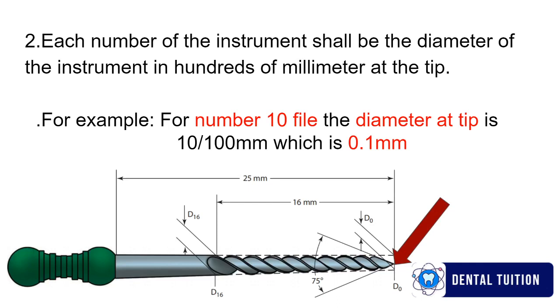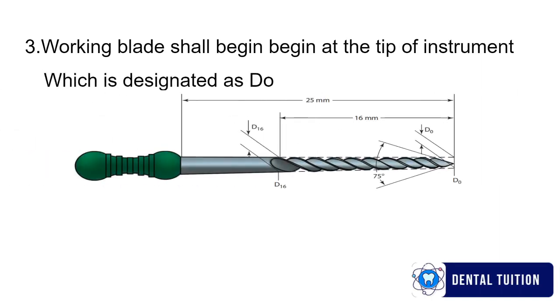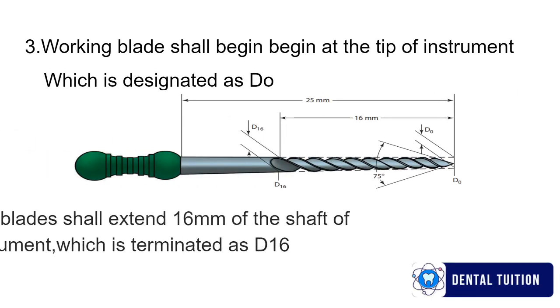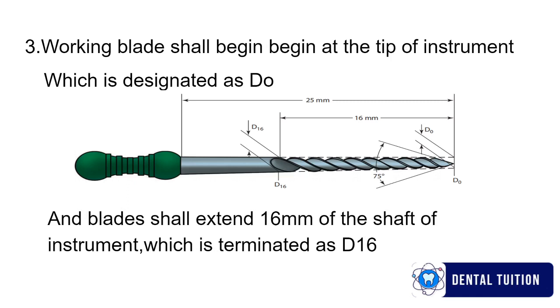Now next recommendation we are going to discuss is that the working blade shall begin at the tip of the instrument, which is designated as D0, and the blades shall extend 16 millimeters from the tip of the instrument, which is terminated as D16.